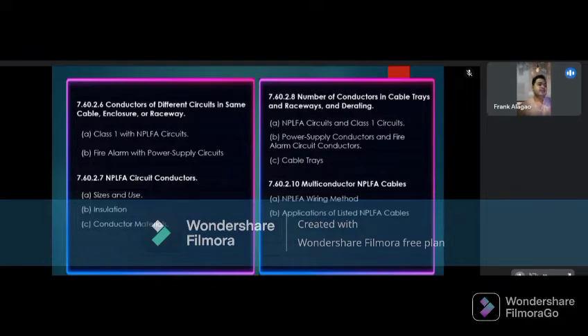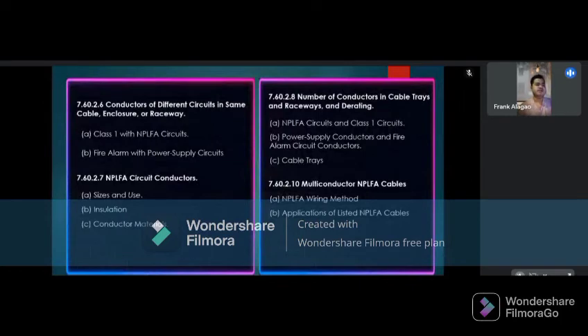Next are power supply conductors and fire alarm circuit conductors. Where power supply conductors and fire alarm circuit conductors are permitted in a raceway, number one, the derating applies to all conductors where the fire alarm circuit conductors carry continuous load in excess of 10% of the capacity of each conductor and where the total number of conductors is more than 3. Number two, it applies to the power supply conductors only where the fire alarm circuit conductors do not carry continuous loads in excess of 10% of the capacity of each conductor and where the number of power supply conductors is more than 3.